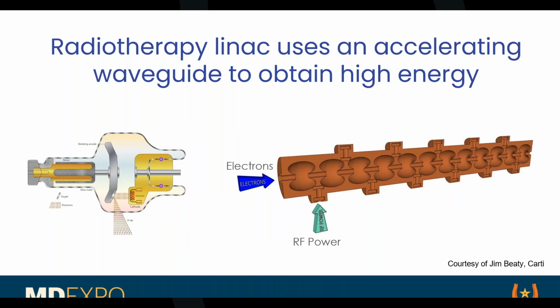So rather than using direct acceleration like a traditional X-ray tube, we use what's called the linear accelerator. That's the device on the right here. We have a number of cavities, these cavities over here. We feed in microwave power, RF power, into the accelerator, and the microwaves populate all the cavities. In each cavity, this generates a potential, a voltage that's pointing in the right direction. Because of the way it's organized, the timing of how the microwave fills the waveguide, and how that potential flips, if we introduce electrons over here, they get accelerated to a higher energy as they go through each cavity. The energy we reach depends on the number of cavities we have. So if you want a higher energy, you just add more cavities.